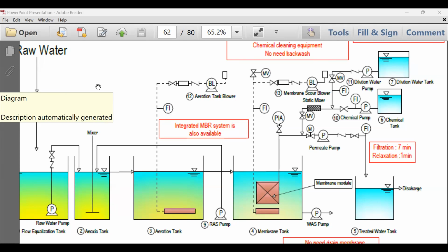Membrane scouring blower. This is the blower used to supply air to clean the modules. Select the blower based on the volume required for cleaning of modules, water depth, etc. If the same blower is used for both biological processing and membrane scouring, the volume of membrane scouring air remains constant at the designated value.